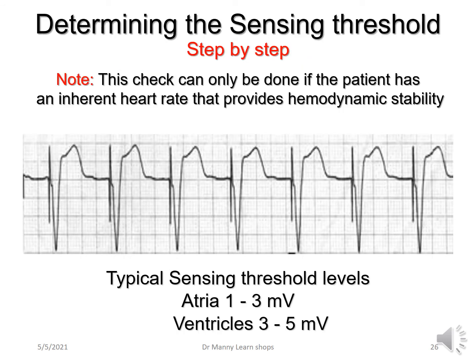The next step is determining the sensing threshold, which is a step-by-step process that is a little more complex. However, this can only be done if the patient is hemodynamically stable — meaning they must have an inherent heart rate providing a normal blood pressure reflected by a normal cardiac output. Typical sensing threshold levels in the atria are one to three millivolts, and in the ventricles, three to five millivolts.